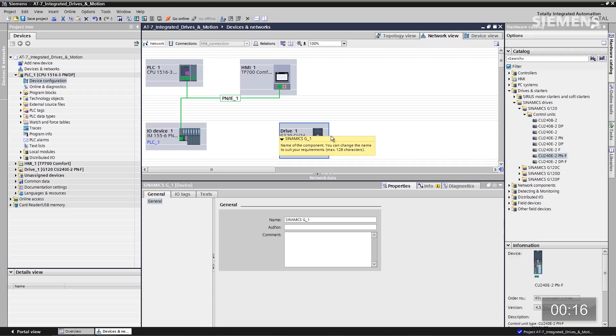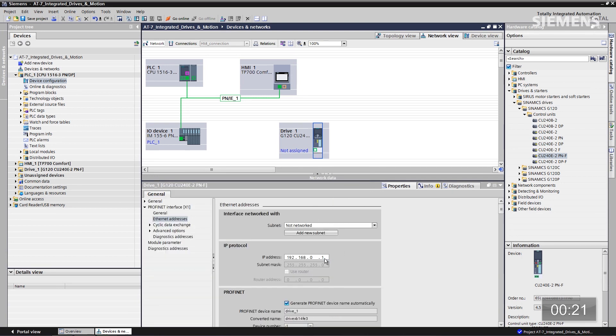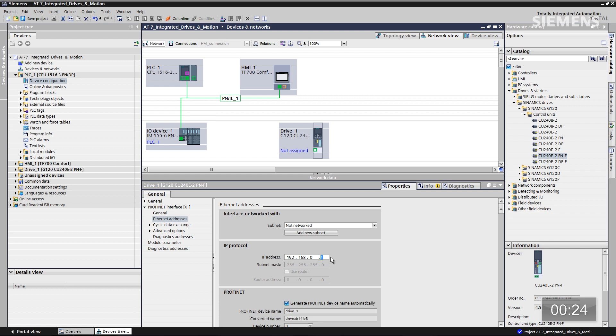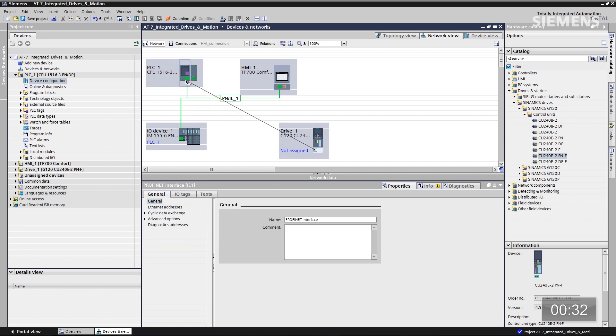Now that I have the photorealistic view of it, let's change an attribute. Let me give focus to it, right-click and go down to Properties. Now if I want to change the attribute of the IP address to 192.168.0.7, and if I want to network it, all I have to do is mouse over the interface and drag and drop that up to our S7-1500 controller. Now it's networked.